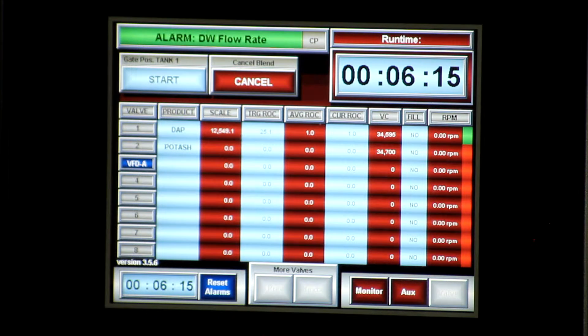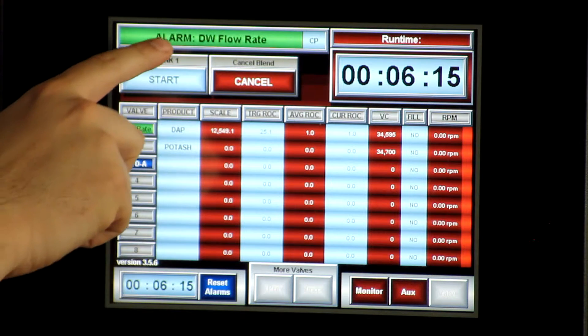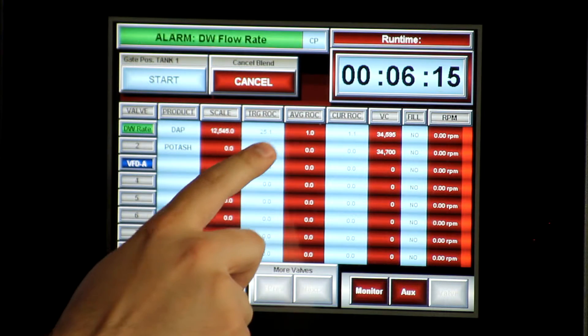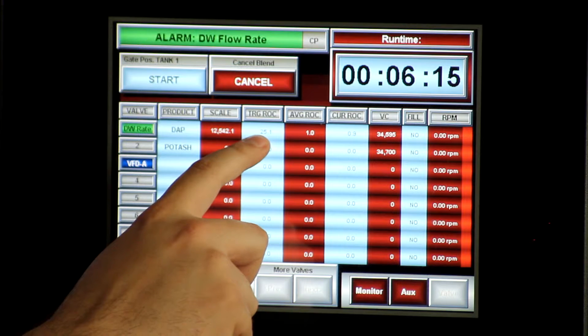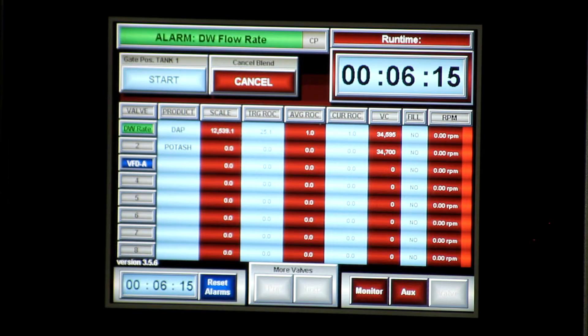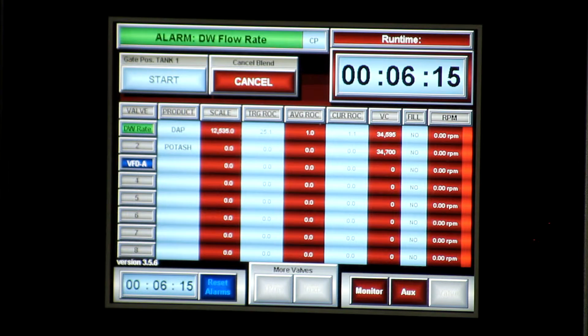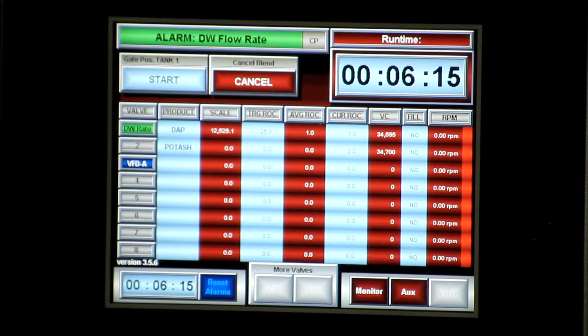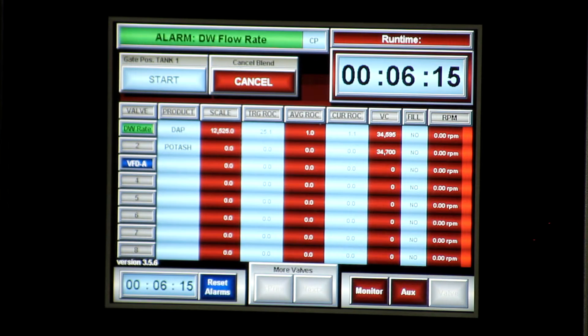In this particular case, you see that you received a DW flow rate alarm on number one, and you see your target was 25.1, yet your current was only one pound a second. What happened was your RPMs spiked up to 90 RPM, and after two program cycles it kicks you out on a DW flow rate alarm because you can't lose enough product.